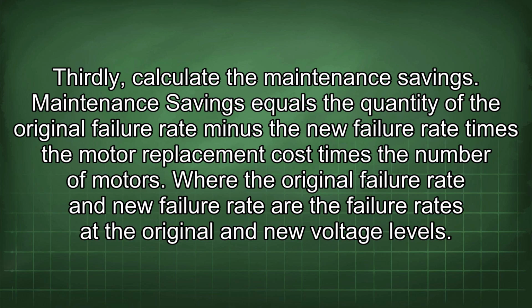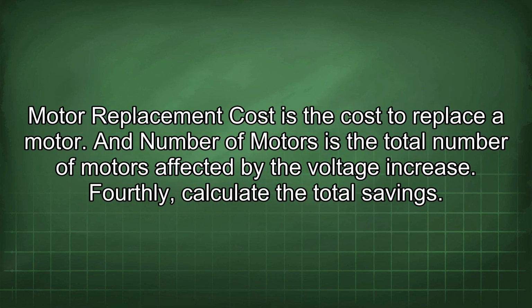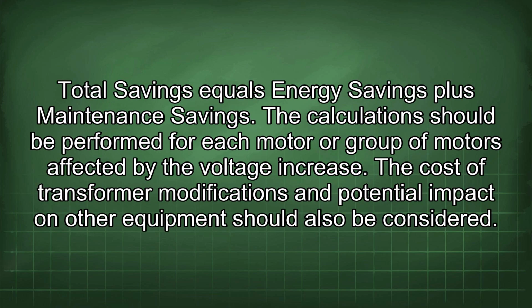Maintenance savings equals the quantity of the original failure rate minus the new failure rate, times the motor replacement cost, times the number of motors, where the original failure rate and new failure rate are the failure rates at the original and new voltage levels. Motor replacement cost is the cost to replace a motor, and number of motors is the total number of motors affected by the voltage increase. Fourthly, calculate the total savings. Total savings equals energy savings plus maintenance savings.